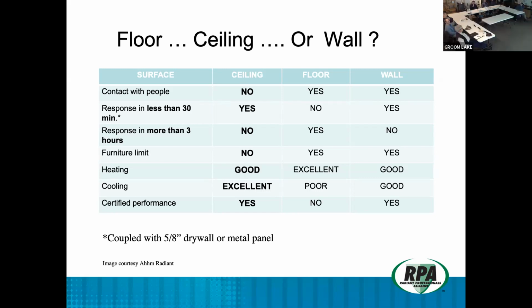It would depend on the radiant tubing manufacturer to provide you with that information. And it's based on the amount of sheetrock that you put over it, which is basically resistance value. And it works out to, I've got the numbers someplace bouncing around in my head. You lose the convective capacity of a ceiling. You've got 100% radiant, but with a radiant floor, you have convective and conductive and radiant. And when you're dealing with a ceiling, you're dealing primarily with just radiant, period. There is no conduction and there is no convective at all. So you have to calculate it based on water temperature, tube density, resistance values of the sheetrock that are being applied.